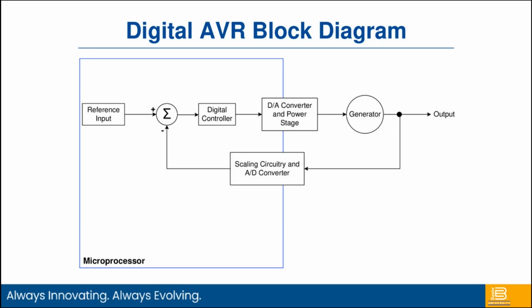We take that digital signal and turn it back into an analog output, or through our power stage, we're going to turn that into DC that's going to be put into the exciter field, in the case of a voltage regulator. Just like an analog voltage regulator, we've got that DC voltage. As we raise it, we're going to increase or decrease the output of that generator.